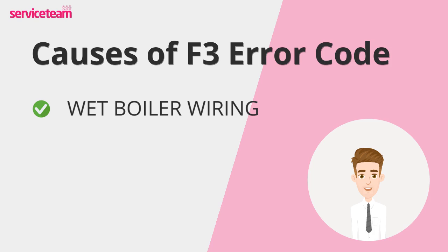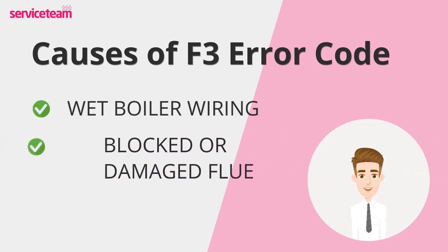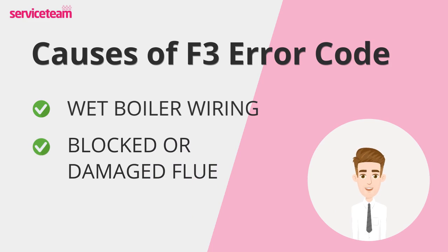Wet boiler wiring can cause several boiler issues, including the F3 fault code. Leaks from the heat exchanger or pump can lead to wet wiring, which triggers error codes and can cause the PCB to malfunction. A blocked or damaged flue also prevents the fan from expelling waste gases, triggering the F3 code. Regular flue maintenance is crucial to prevent this issue.